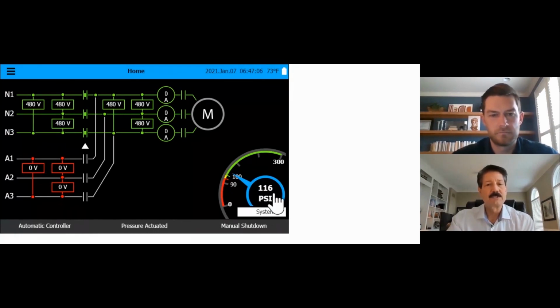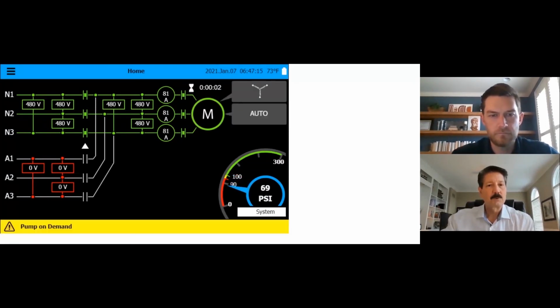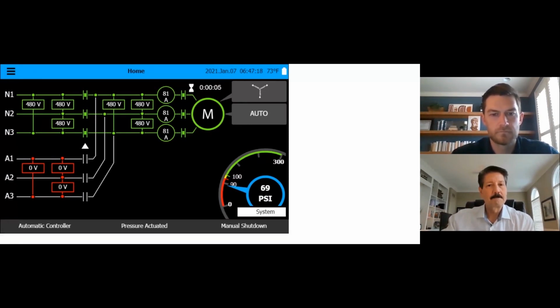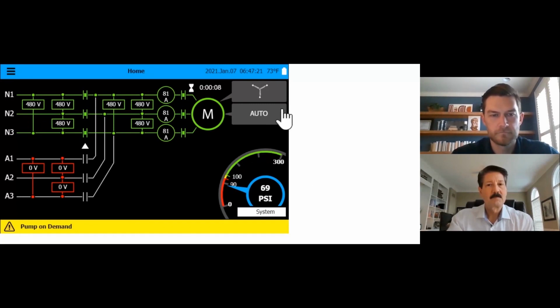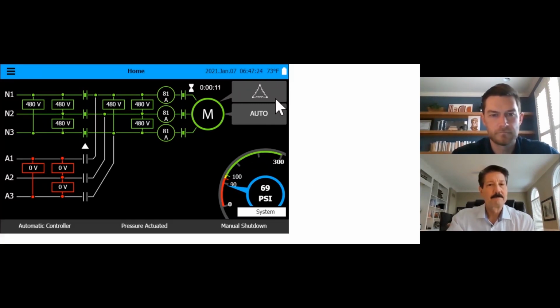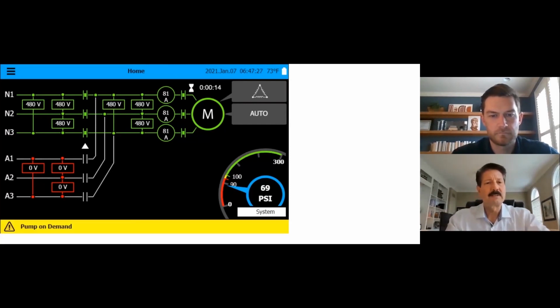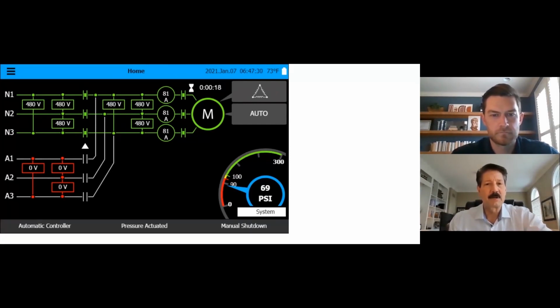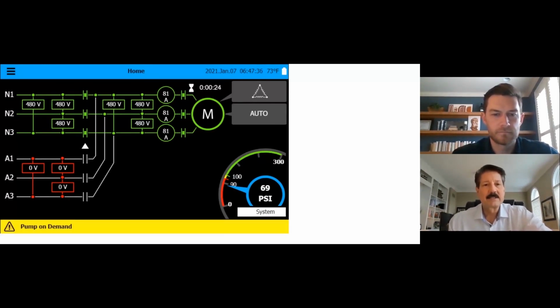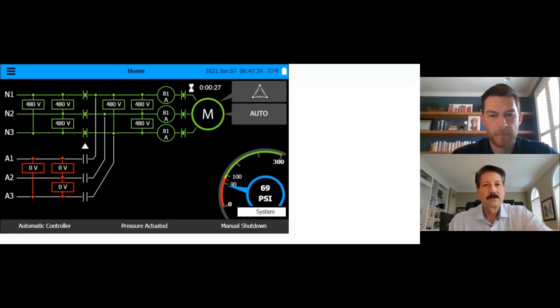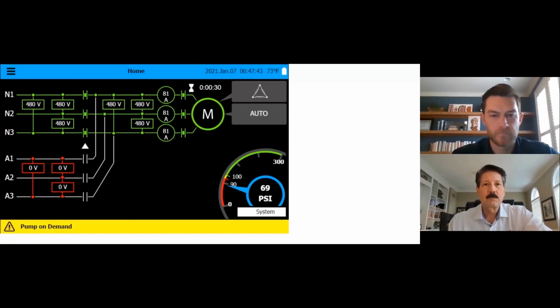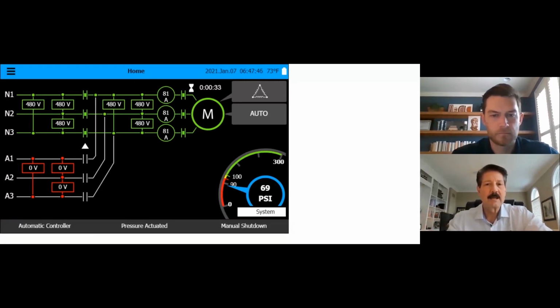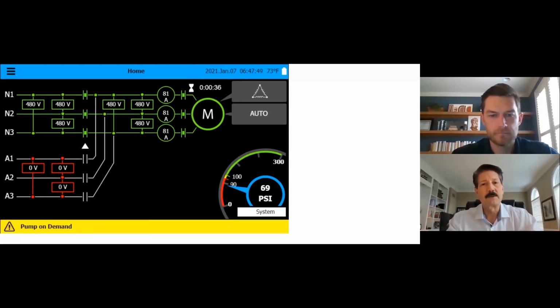So what I'm going to do here is do a system pressure drop. Watch the PSI on the bottom right side. It's visual. Take a look at the screen. Top right, we see it's a Y delta. So for the techie people, literally, we have the icons for each of the types of controllers that are available, whether it's a Y delta, across the line delta itself, a solid state, soft start, or you can even do an auto transformer. Any of these, the icon would pop up in that top right side for people that want to know, and it'll tell you what type of controller you actually have.